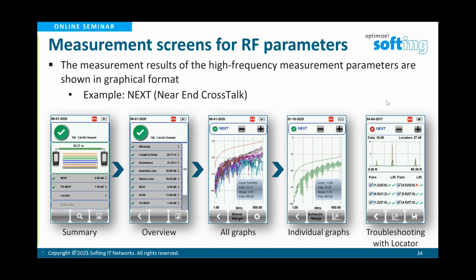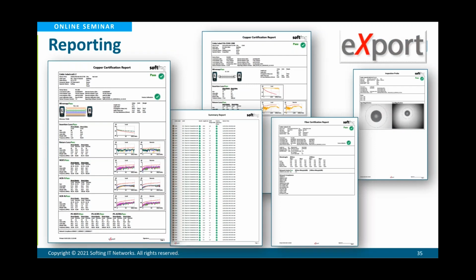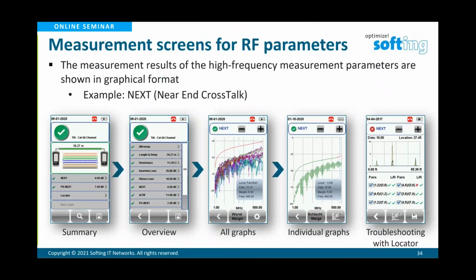What we want to highlight is that we have a time domain NEXT locator function built in for both NEXT and return loss parameters, so most faults in the high frequency area can be found very easily with this function. For this, we perform vector measurements inside the unit, then apply a fast Fourier transformation into the time domain and represent it as a graph. In this case, something in the middle of the link affected the NEXT fairly significantly. It may have been clamps someone put between two cables, but I cannot say for certain since I did not measure that link myself.